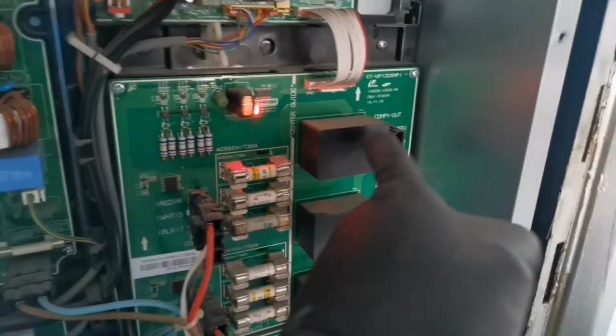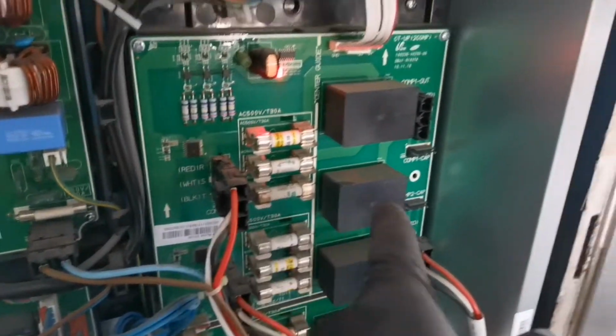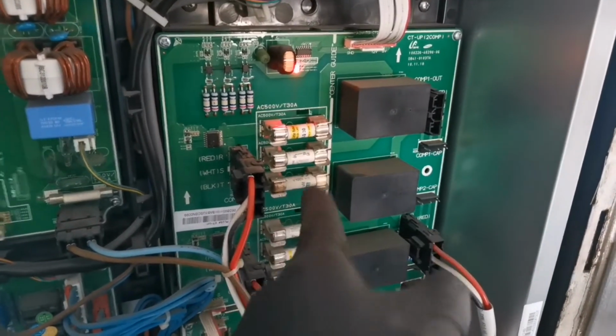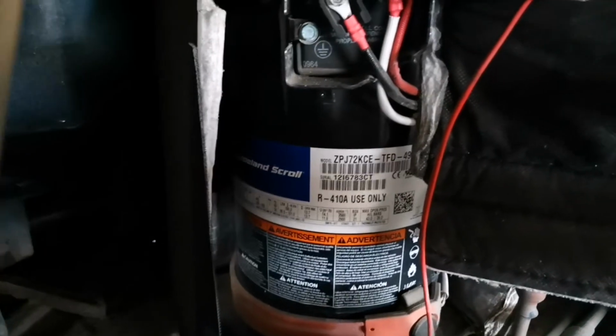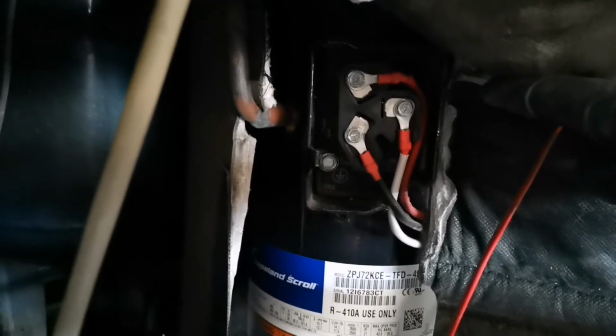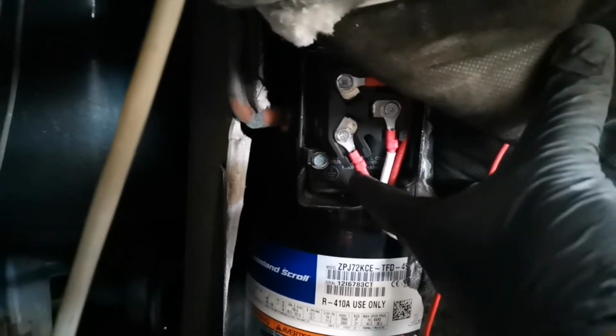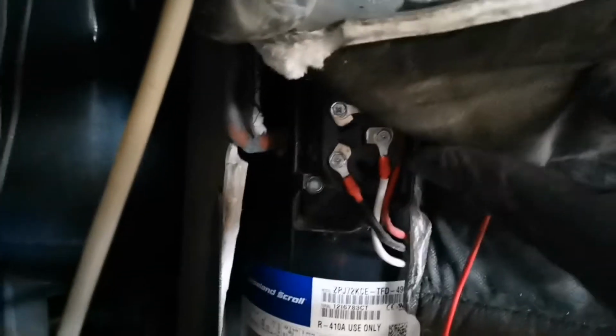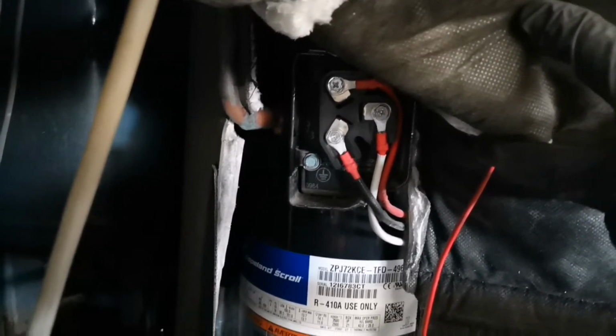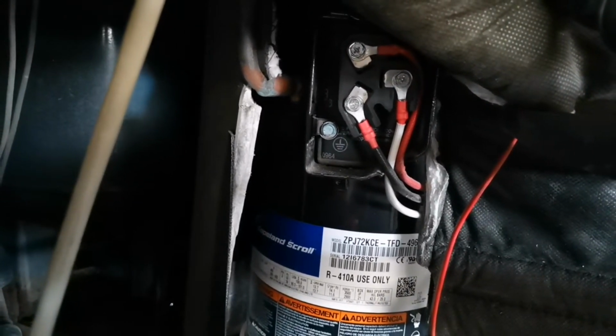Alright guys, so on the north side system, what I've noticed was there was no current draw on the slave condenser on compressor 1. There is voltage across all fuses. You can see that's a fuse that has been changed. Same thing. Found the compressor unplugged, and I've dived in a little bit deeper. As you can see, it's a Copeland scroll R410A system. It's not grounded, but we lost one winding. It's open circuit, so we're going to have to replace that.